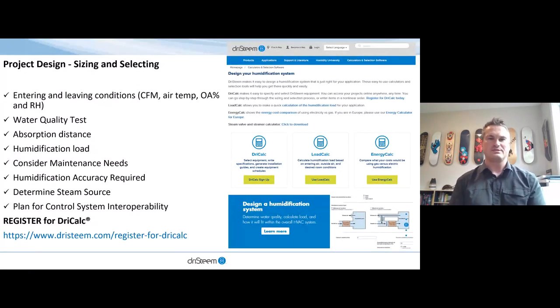But determine the steam source if you're going to use a centralized system. If you're using a steam source off of a boiler that's highly treated with chemicals, it may not be the most appropriate steam to introduce into the occupied environment. A steam exchange process may need to happen for that. And then plan the control system. How are you going to control the system? Is it through a building automation system? Is it a localized demand signal? Those are factors that need to be considered as well.